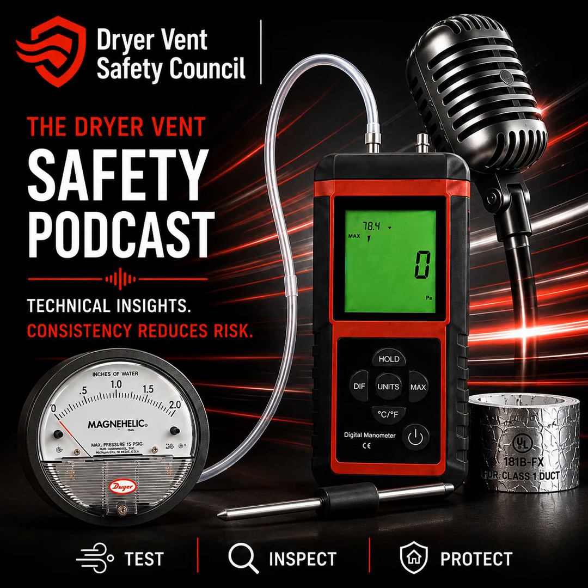They look at the screen. What number are they looking at? Because the industry uses inches of water column, but this DVSC method specifically uses pascals, abbreviated as PAS. Right, and what's fascinating here is the rationale behind shifting to pascals. You have to evaluate this from the perspective of human factors engineering. Oh, so the goal wasn't laboratory-grade granular precision. The goal was a foolproof, simple, repeatable field diagnostic for humans in difficult environments. Digital manometers generally display pascals directly in clean, whole numbers. And 1 inch of water column equals roughly 249 pascals, so it offers drastically finer resolution.